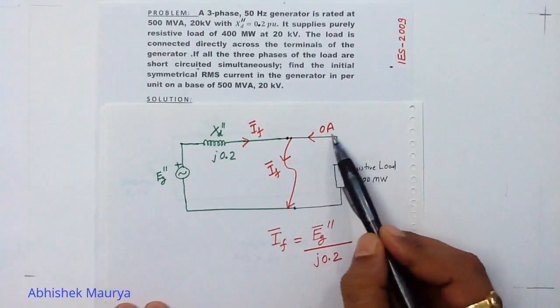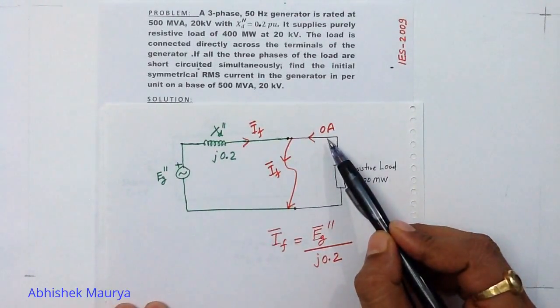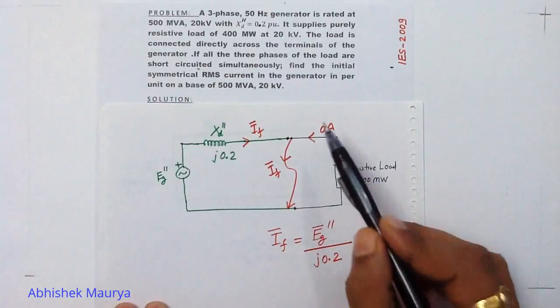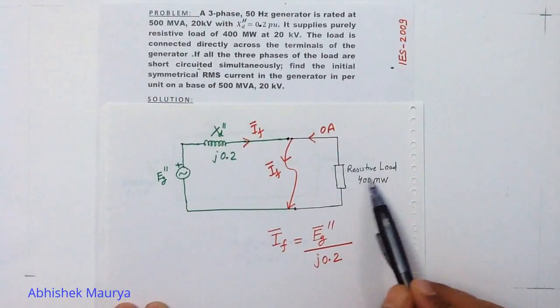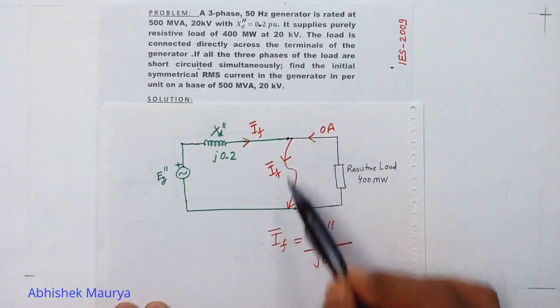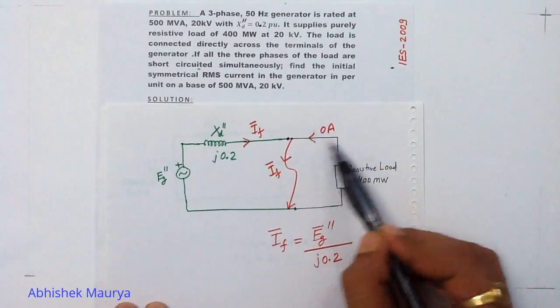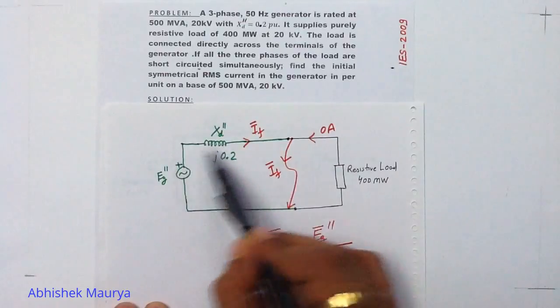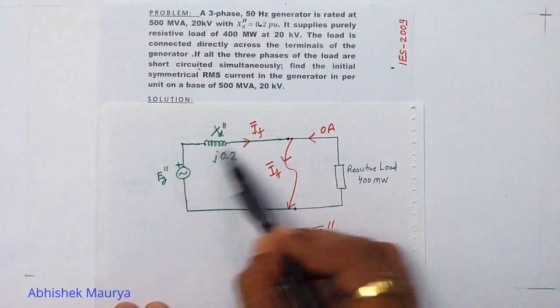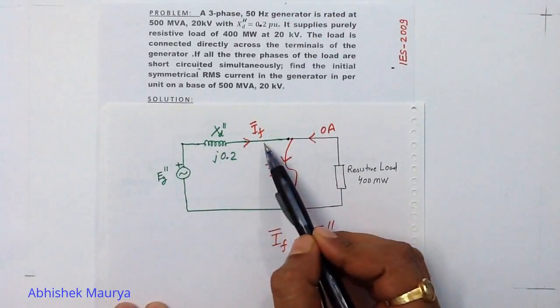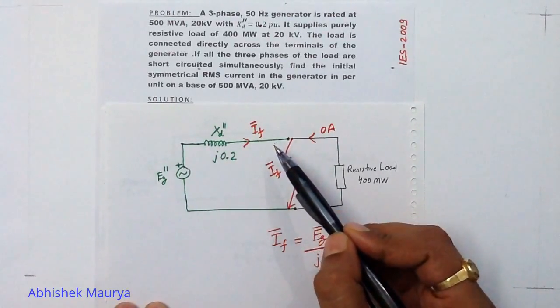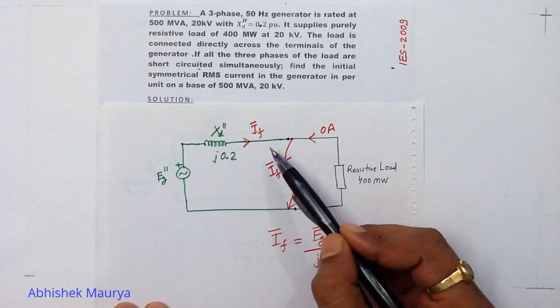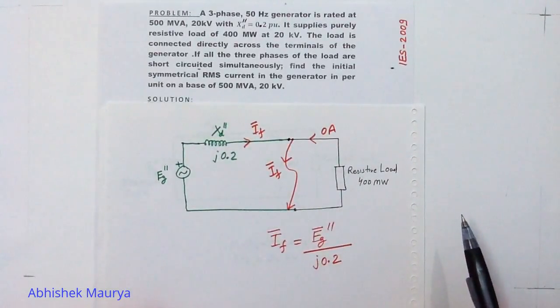Here I have written 0 ampere. The load given is resistive, and during the fault a resistive load cannot feed fault current. That's why 0 ampere is written here — the complete fault current will be fed by the generator. There are three names for IF: it is called fault current, sub-transient current, or initial symmetrical RMS current.